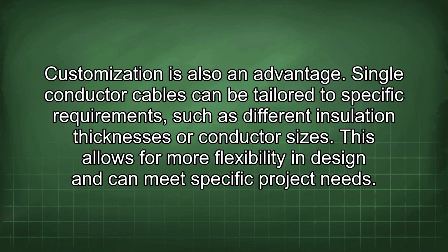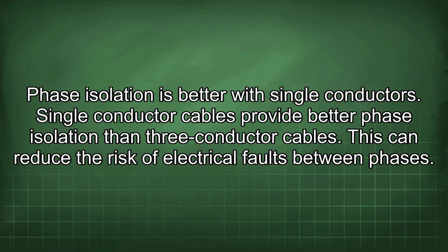They can be easier to bend and install in tight spaces or around obstacles. Customization is also an advantage. Single-conductor cables can be tailored to specific requirements such as different insulation thicknesses or conductor sizes. This allows for more flexibility in design and can meet specific project needs. Phase isolation is better with single conductors. Single-conductor cables provide better phase isolation than 3-conductor cables. This can reduce the risk of electrical faults between phases.